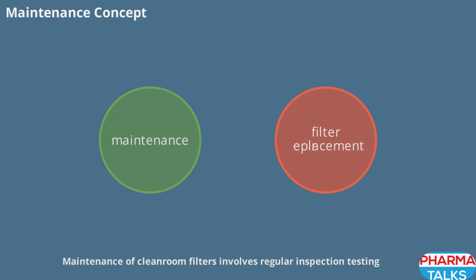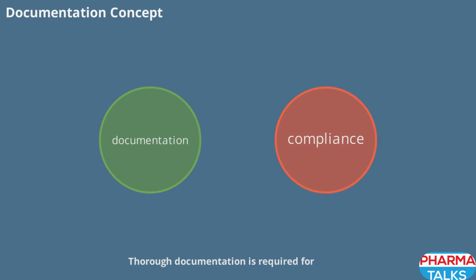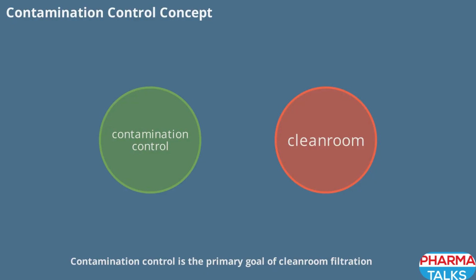Maintenance of cleanroom filters involves regular inspection, testing, and replacement as needed. HEPA filters are generally easier to maintain than ULPA filters, which require more robust systems and careful handling due to their higher efficiency and pressure drop. Thorough documentation is required for all aspects of cleanroom filter installation, validation, and maintenance. This includes test results, maintenance records, and compliance reports, ensuring traceability and regulatory adherence. Contamination control is the primary goal of cleanroom filtration. Both HEPA and ULPA filters play a vital role in preventing airborne particles from compromising sensitive products and processes, ensuring product safety and quality.